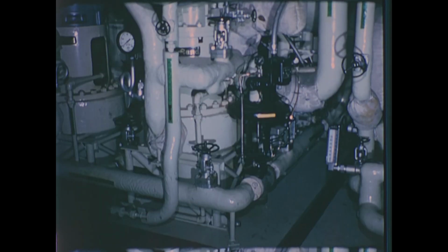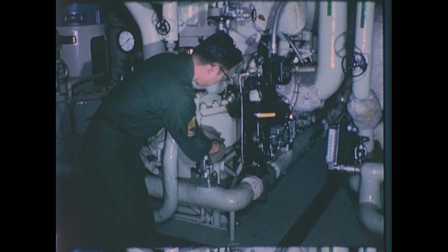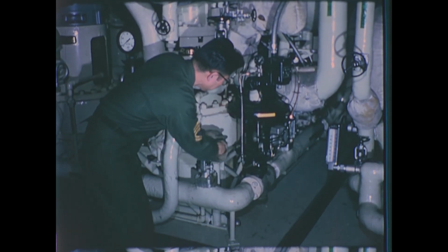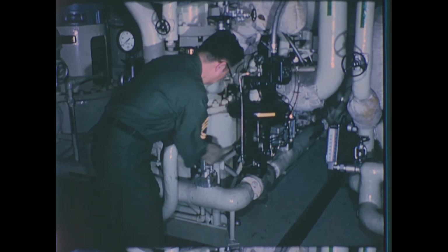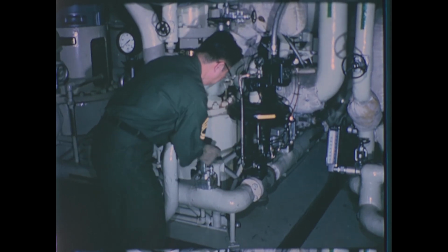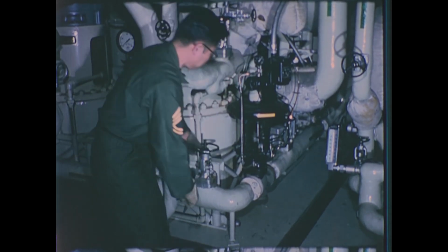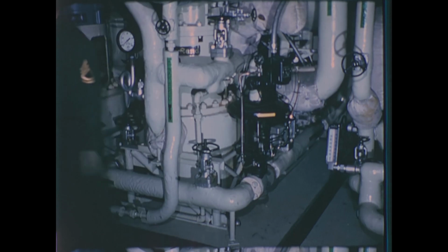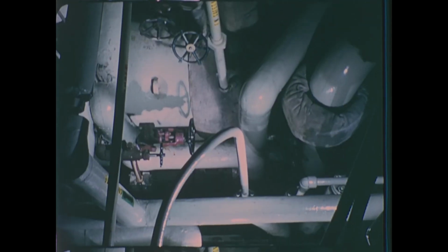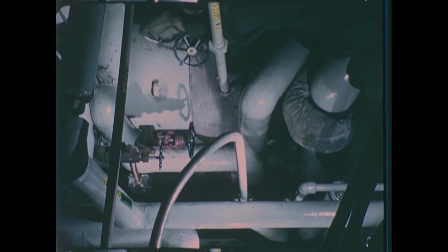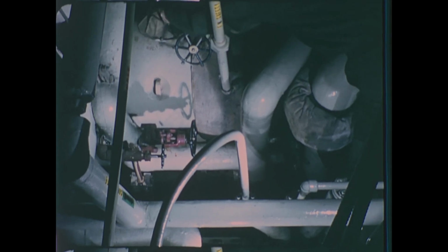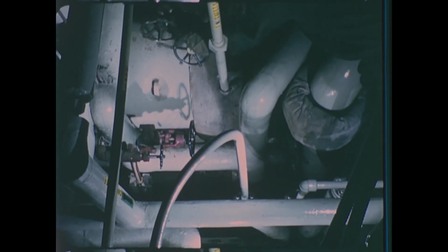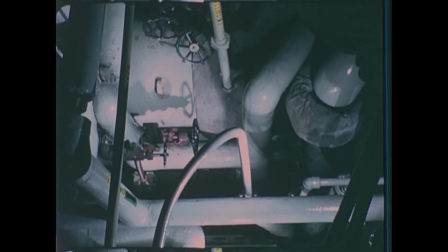Feed water from the feed water heater passes through the flow controller located in the HTA package and goes directly to the steam generator. Here, the operator opens the feed water flow controller isolation valve, lining up valves to the feed water heater. This heater takes steam from the first stage of the turbine to preheat the feed water before it enters the steam generator.